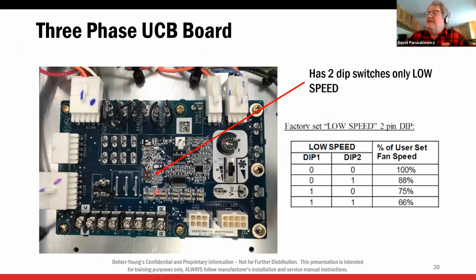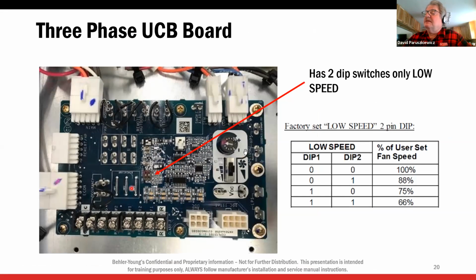Now on the 3-phase board, you have this single or 2 little dip switch setting right here. And remember I said on the 5-ton and over, we have a 2-speed blower. That dictates what speed the blower will be on low speed. So the factory default will be 66%, both switches on. That's for the low speed, so the G speed, circulation speed. All right, so that's dictated by that switch. Again, factory default on the 5 and 6 ton will be both on 66%.